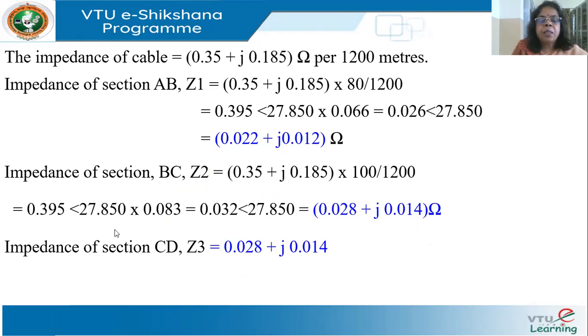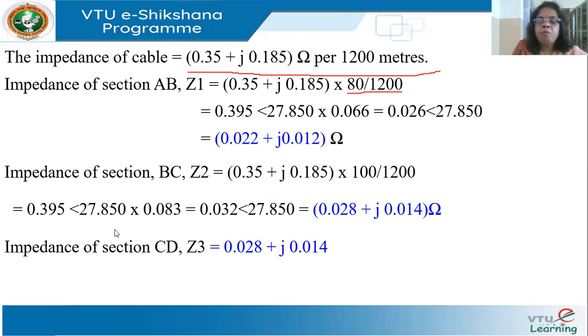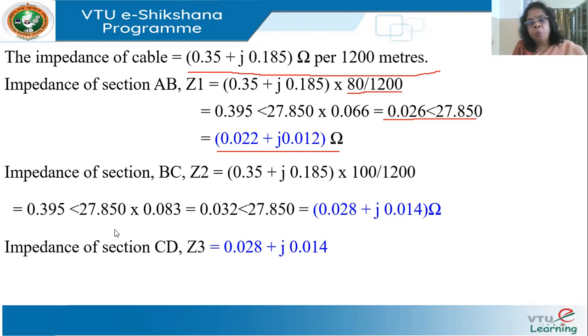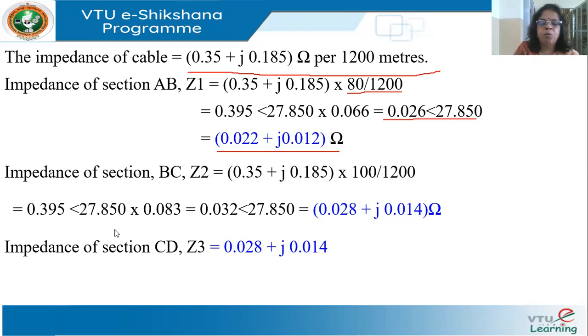The impedance of the cable is 0.35 + j0.185 ohms per 1200 meters. The first section AB is 80 meters, so I multiply by 80/1200. Section BC is 100 meters, so I multiply by 100/1200. Section CD is also 100 meters, so Z3 equals Z2. I represent each impedance in both polar and rectangular form so I can pick whichever is needed — polar for multiplication, rectangular for addition.